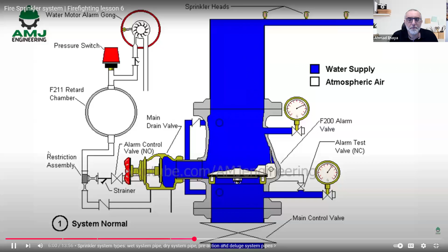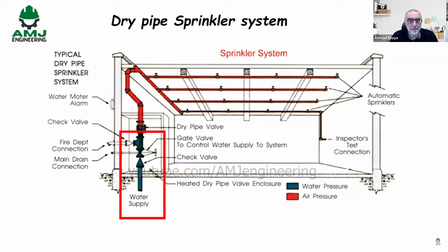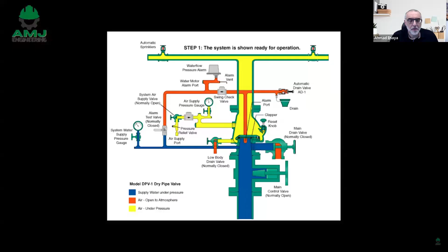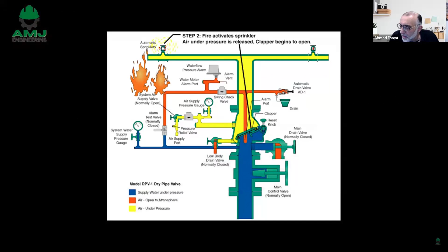Dry pipe fire sprinkler systems. Dry pipe systems are very similar to wet pipe systems with one major difference. The pipe is not constantly filled with water. Instead, the water is held behind a dry pipe valve, usually some distance away from where the sprinklers are located. Like a wet pipe system, when the temperature at the ceiling becomes hot enough, the glass bulb or fusible link of the sprinkler breaks. However, in this case, water isn't immediately available because the pipe is not water-filled. As mentioned, during the heat, the sprinkler detects the heat. When there is heat, it will open. When it opens, the gas pressure here will be low. So this will trigger the valve to open and then will push the water inside the pipe. This is the dry.